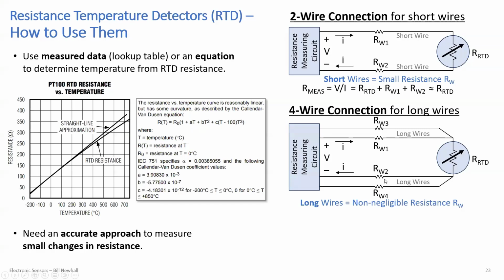So what you can do is add 2 more wires. You use wires 3 and 4 for a voltage measurement, and wires 1 and 2 to flow current. You'll have a voltage drop across wire 1 and wire 2, but you'll know the current, since the current is going through the RTD, not anywhere else.